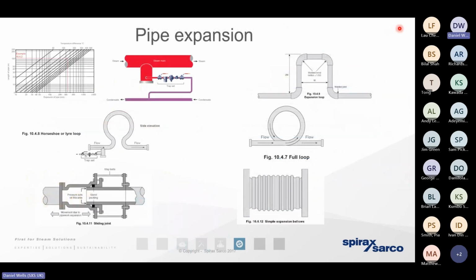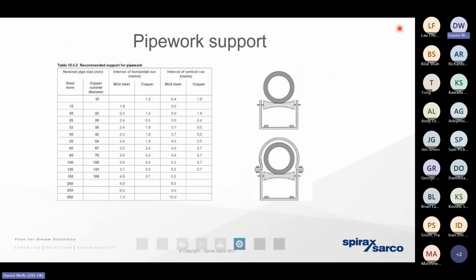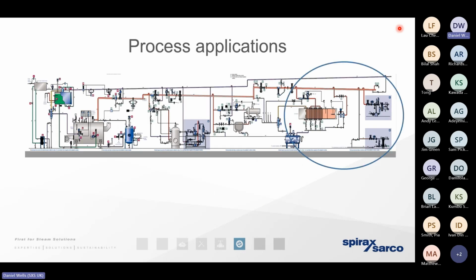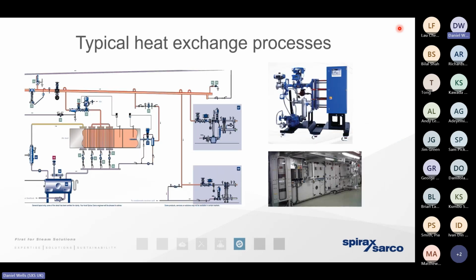Other things to think about: a steam infrastructure, high temperature, high pressure, then we are going to have some expansion. We need to calculate what that expansion is likely to be and mitigate against that expansion and understand how and where to anchor different items of capital equipment. Same with pipe supports. If we've got too few pipe supports, the risk is that pipework could sag under its own weight, and it's then trapping that condensate. So we need to follow that best practice, not only to generate the best quality of steam in the boiler house, but to make sure that we're moving the steam with the best design considerations in that infrastructure in the middle. And that's so we can get the best quality of steam into the plant room.